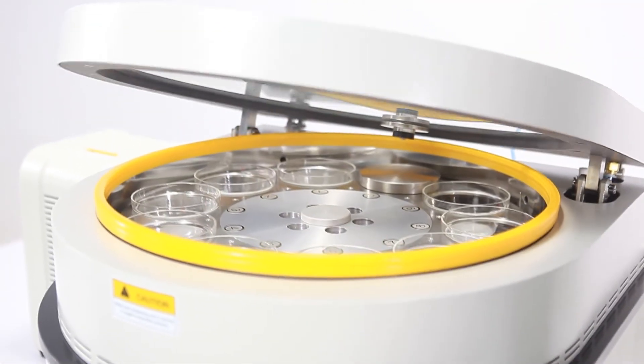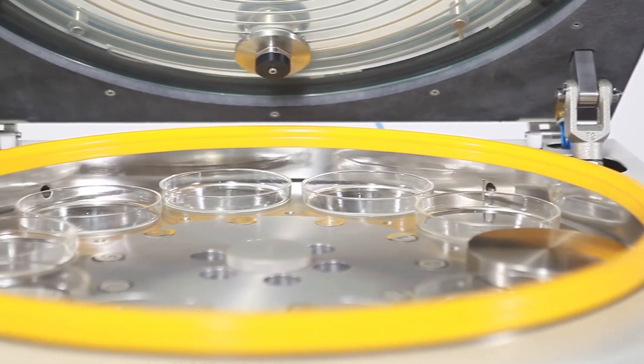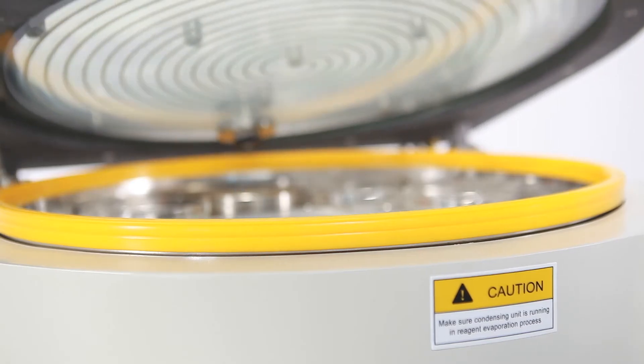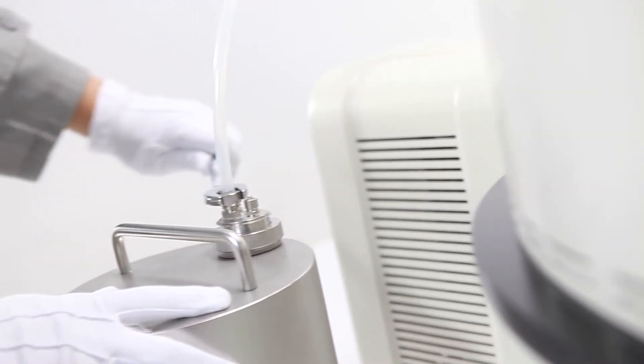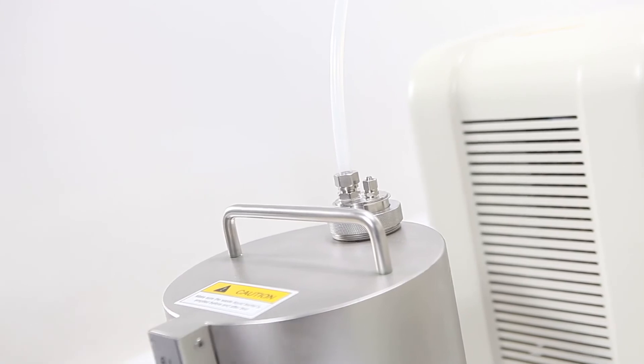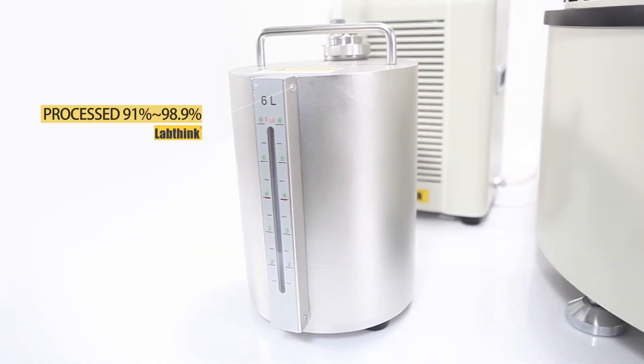C830 is featured with fast evaporation technique and high efficiency in automatic structural design, which can maintain the reagents at optimum evaporation status close to boiling. With gas balancing technology, the concentration of evaporated reagent can be reduced quickly in the fully sealed environment, which avoids the risks of reagent vapor leakage. 91% to 98.9% of waste reagents can be processed by the simplified and high-efficiency reagent recycling system.